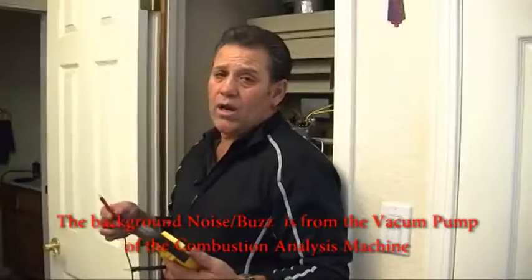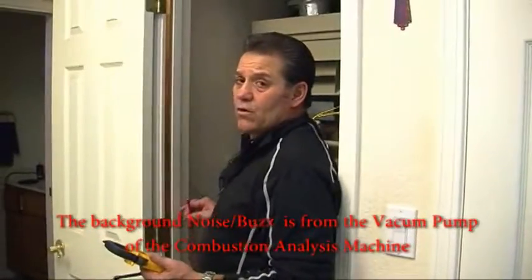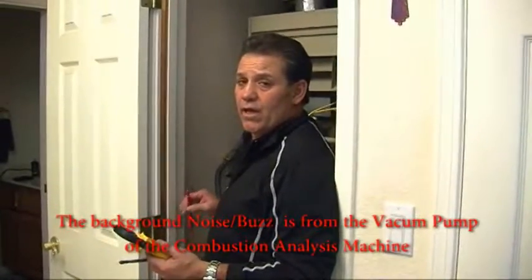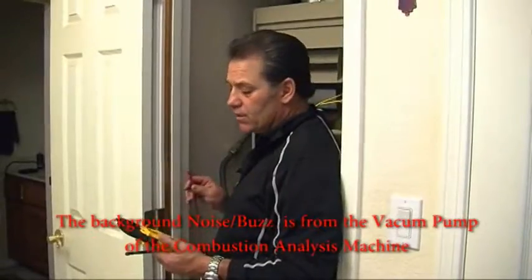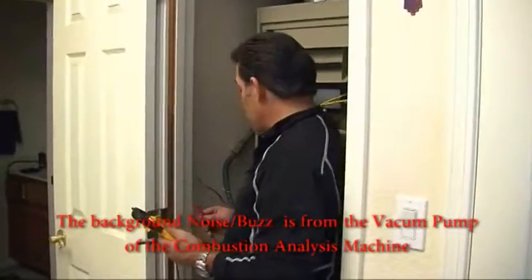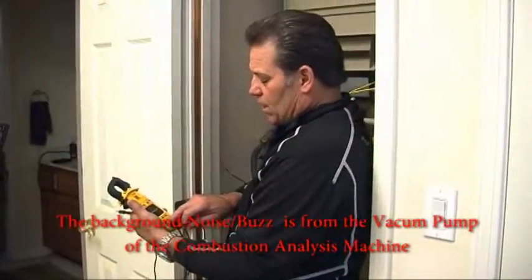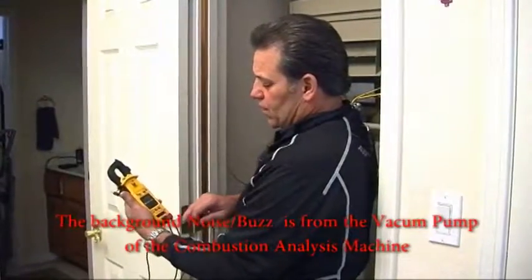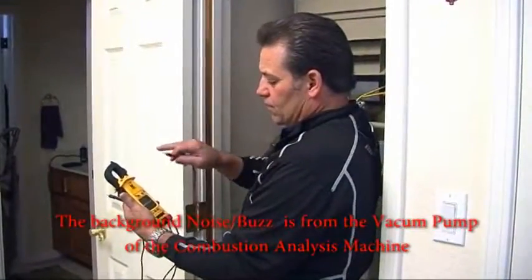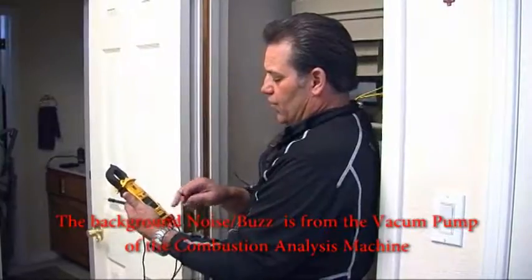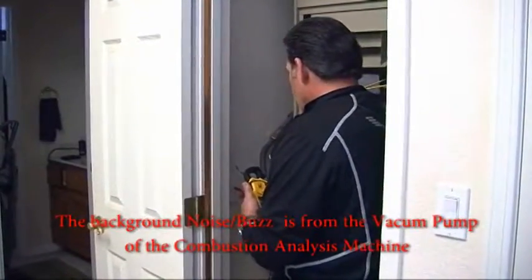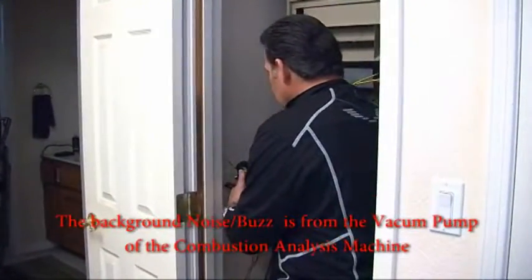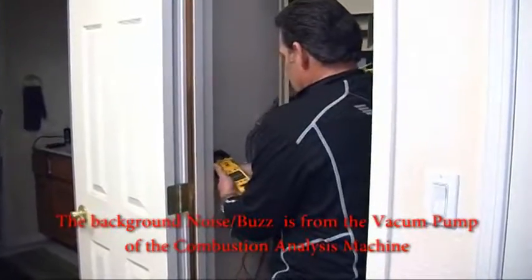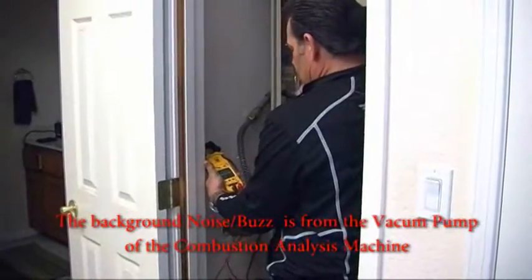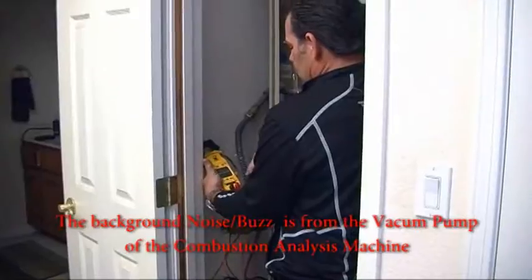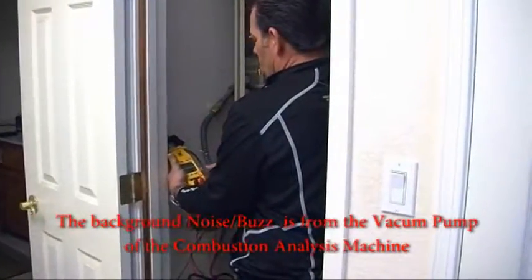Okay, while I'm working on the furnace, we've checked for correct continuity, and we've checked to see that we do have voltage there. I just want to do a test to see what voltage I do have. I've set my meter on voltage. It's a kind of swirly line with a V. So I'm going to go ahead and plug this in and make sure that I've got 119.9 volts, 119.8. So I'm right where I want to be.